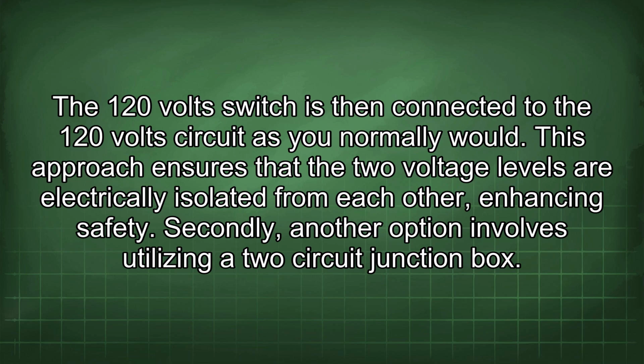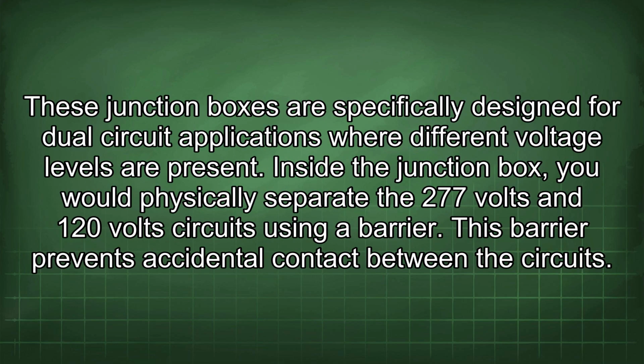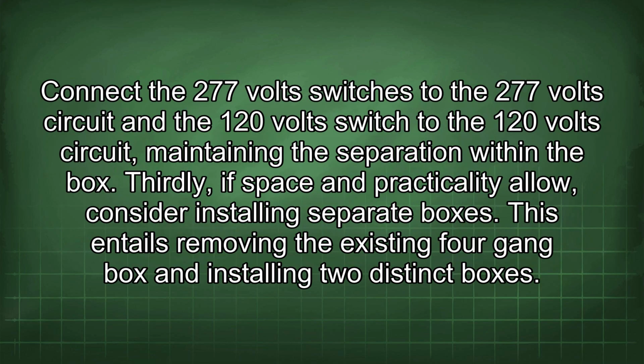Secondly, another option involves utilizing a two-circuit junction box. These junction boxes are specifically designed for dual-circuit applications where different voltage levels are present. Inside the junction box, you would physically separate the 277 volt and 120 volt circuits using a barrier. This barrier prevents accidental contact between the circuits. Connect the 277 volt switches to the 277 volt circuit and the 120 volt switch to the 120 volt circuit, maintaining the separation within the box.